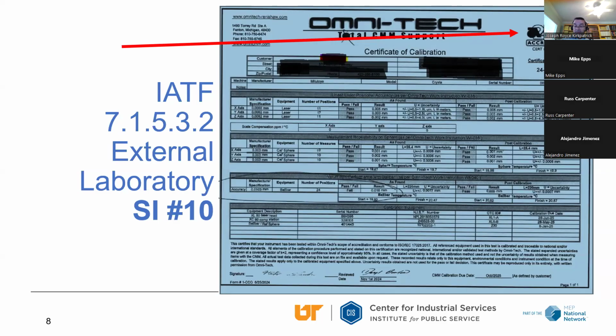Sometimes, Joe, would it be because they charge extra for it? Like it's an extra service that they're accredited to, if it's on their accreditation scope. It is. That's the main reason that some labs don't put it on, is because they want to charge you an extra $300 or $500 for that stamp. And it's kind of a racket. But it is the requirement of the standard. If you don't get that stamp on the certificate, you should at least have a copy of their lab scope that includes that service that they're providing. In this case, they were calibrating a CMM. So they would need to have that on their lab scope.